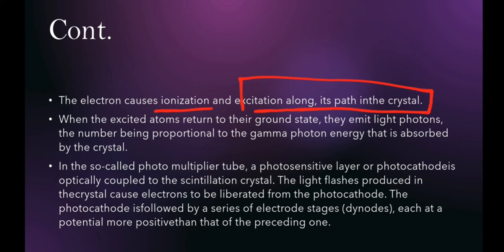When the gamma rays fall on the scintillator, an electron is emitted and this electron causes ionization or excitation along its path in the crystal. When the excited atom returns to the ground state, it emits light photons, and the number of these light photons is proportional to the gamma photon energy absorbed by the crystal.